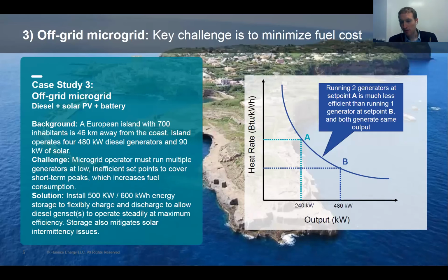So with the battery, adding a battery to a grid like this allows it to charge and discharge rapidly to meet these short-term peaks. Then you can turn off one or two of these engines running on min load and just run two engines at full. This would be considered a spinning reserve replacement for the more technical folks out there. It also helps mitigate any solar penetration issues on the grid, so that if a cloud flies over and solar generation drops suddenly, the battery will be able to accommodate that change.